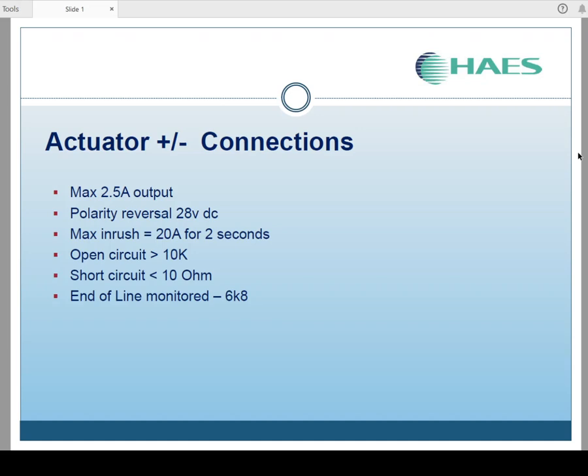For the actuator pos and neg connections for your motor or actuator, the maximum output is 2.5 amps continuous. It's a polarity reversal system, so normally there's no voltage or a small monitoring voltage on those terminals. When you open, they become pos and negative 28 volts. When you close, the voltage polarity reverses to close your motor. It's a maximum inrush of 20 amps for 2 seconds.